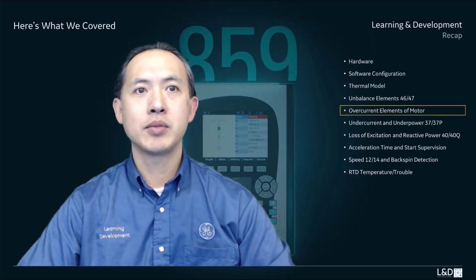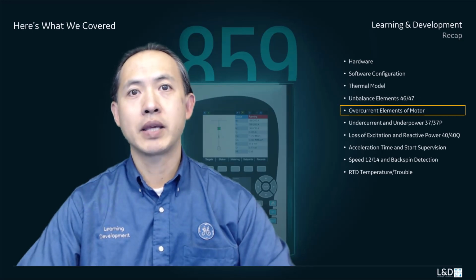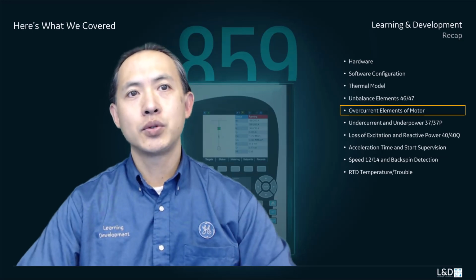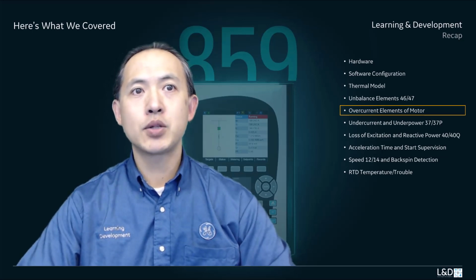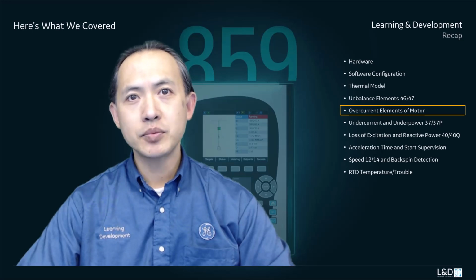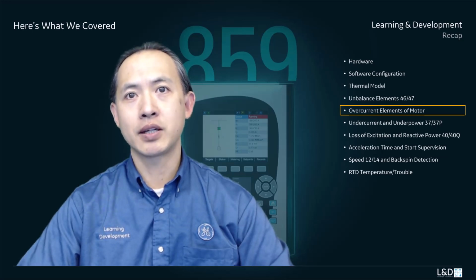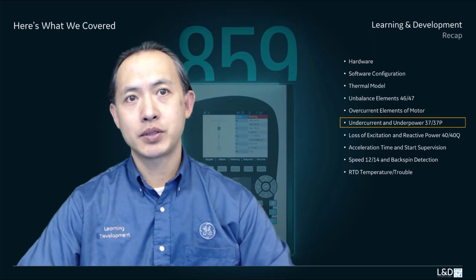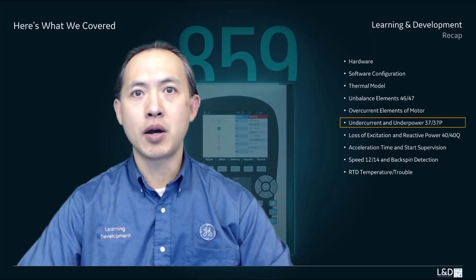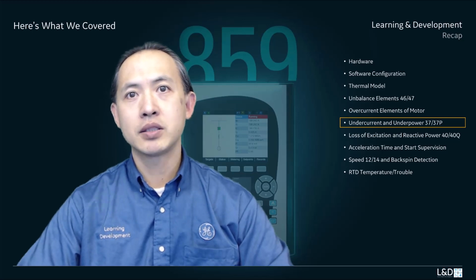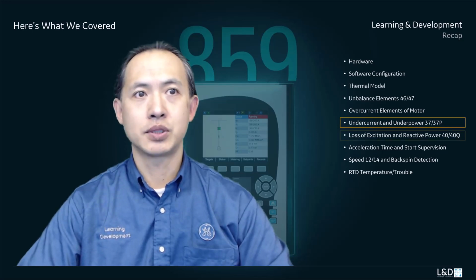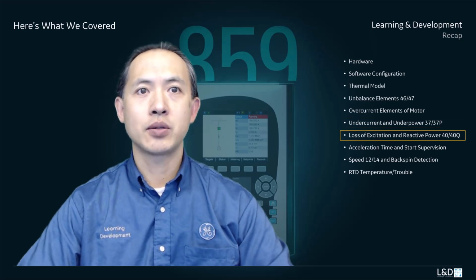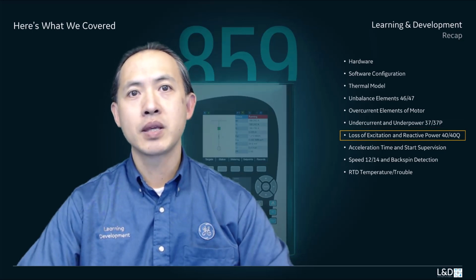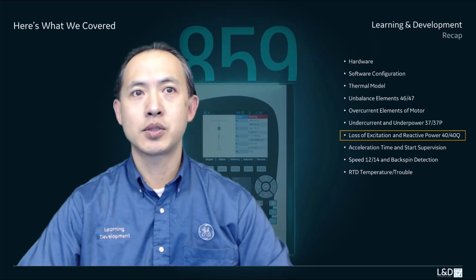In the overcurrent elements of the motors, we introduced the mechanical jam, overload alarm, short circuit, and ground faults. When using the circuit breaker, make sure to use the circuit breaker for the short circuit protection. Don't use the contactor. Then we introduced the undercurrent and underpower 37P. These two elements are used to protect against loss of load. Loss of excitation and reactive power 40 and 40Q: we introduced that loss of excitation is used for synchronous motor protection.